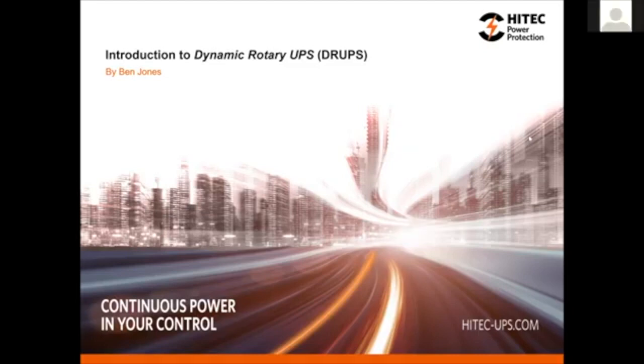Okay. One more. Are there any load concerns when it comes to the type of load when you're specifying your system? Leading power factors, yes. If you're outside of a 0.8 leading to 0.8 lagging power factor window, that might be a concern, but very rarely do we have leading power factor. If you have old motors, pumps that are direct online, so they're 6 times full load current, that probably introduces the problem. But for the most part, no.